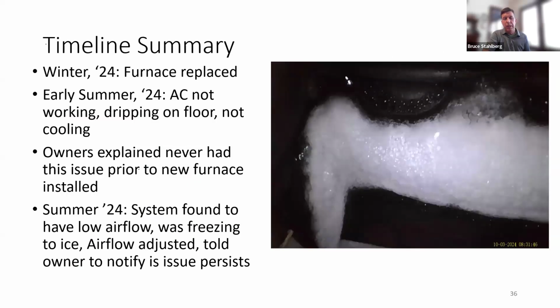So here's an example. A new furnace was installed in the winter of 2024. In the summer, the AC wasn't working, with water dripping all over the floor and not cooling. The owner explained they had never had this issue prior to the new furnace. Somehow I got involved. So I went out there, we did an airflow test. The system was found to have very low airflow and was freezing the coil. That's a picture of the coil there. You cannot blow air through ice. The airflow was adjusted, and I told the owner to notify us if they have any issues, and we haven't heard from them since.